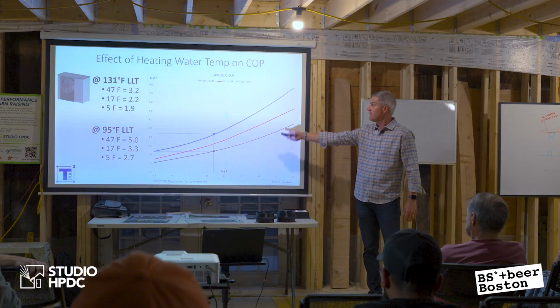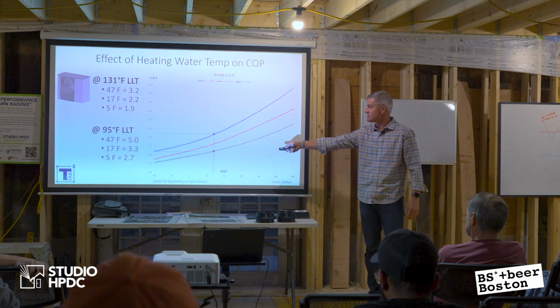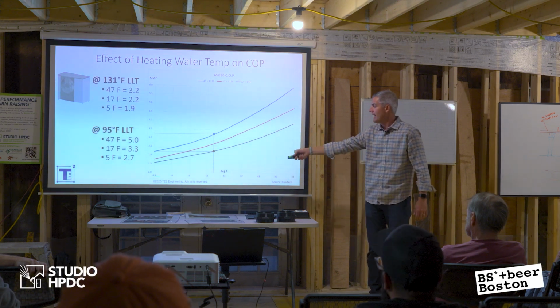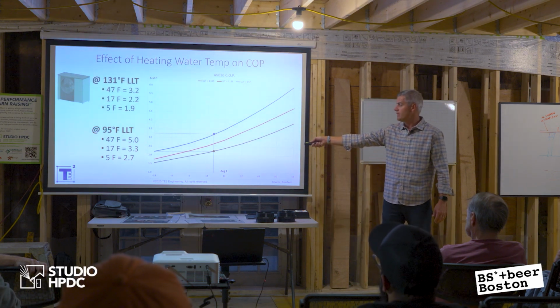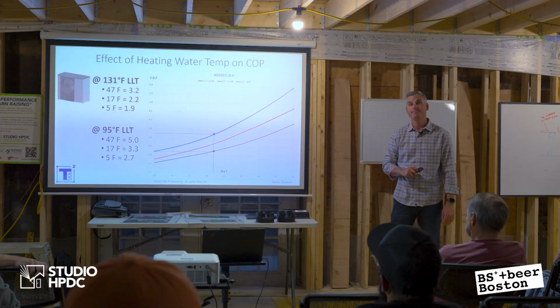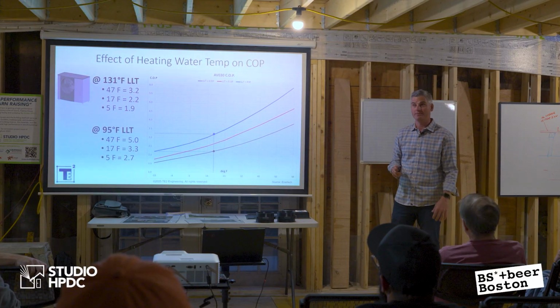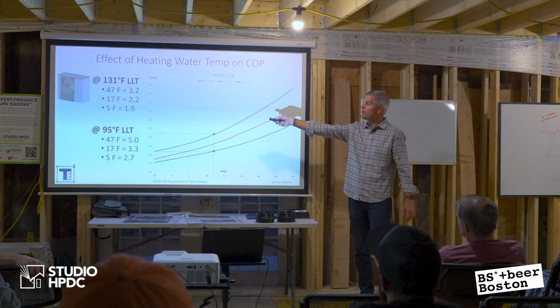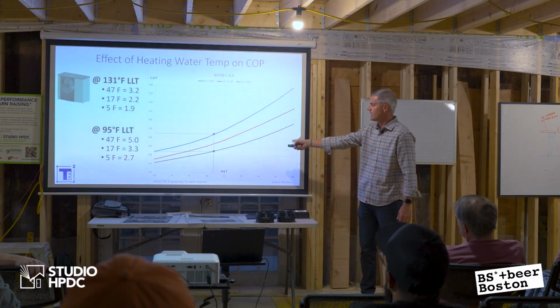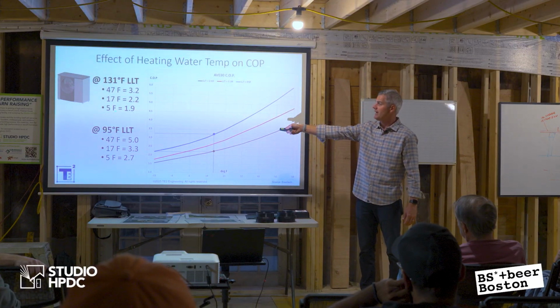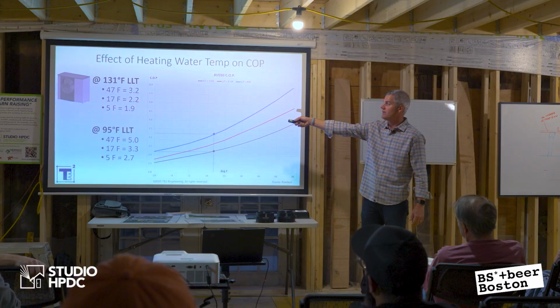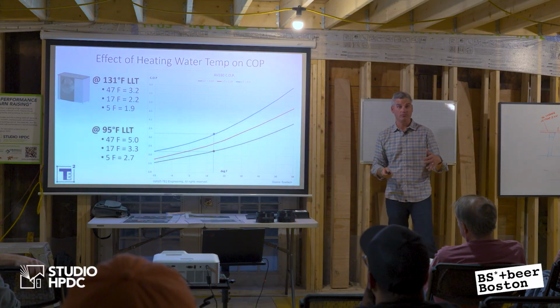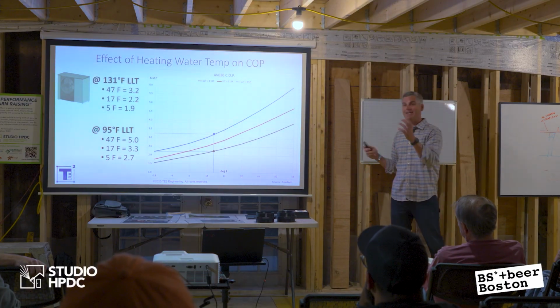So if I look at the 95 degrees, this is the 95 degree temperature at different outdoor temperatures. At -4, it's still going to be at a 2.5 COP. Amazing, right? If I have to jack it up to 131 degrees, my efficiency takes a hit, I go to the black line. So I'm going to go between 1.9 at 5, all the way up to 3.2 at 47. Still better than your traditional mini splits, but it's not as great.